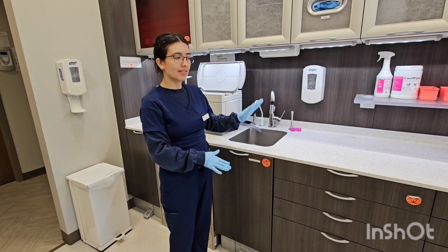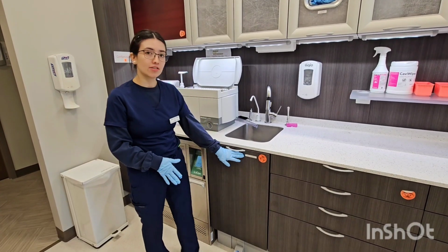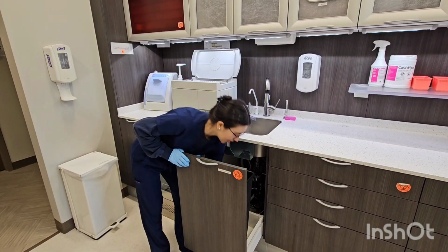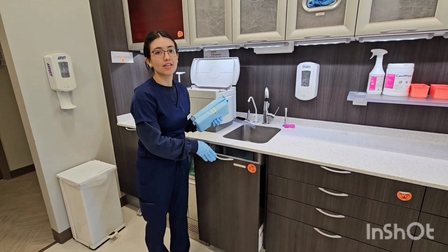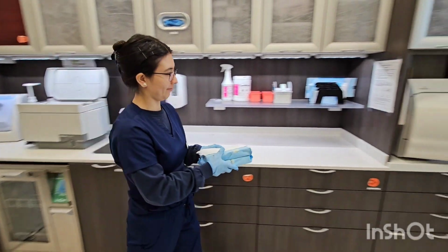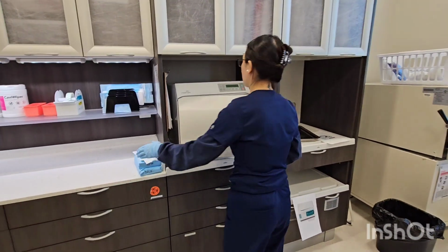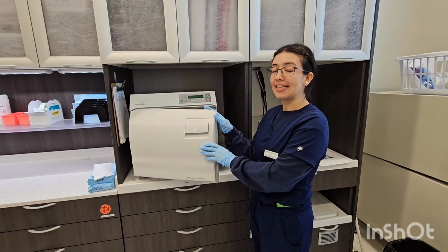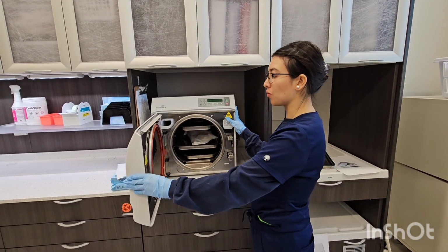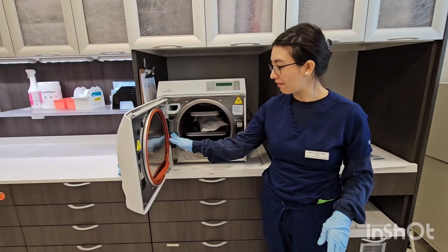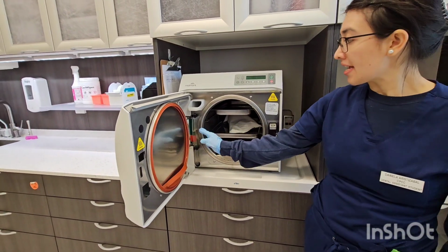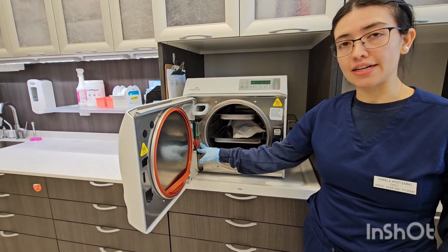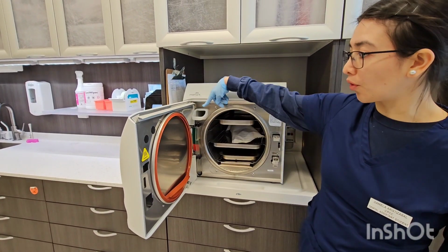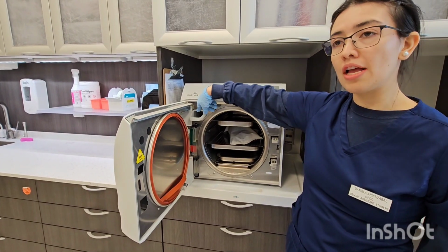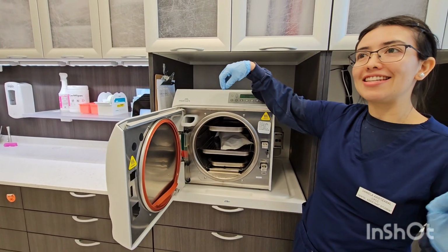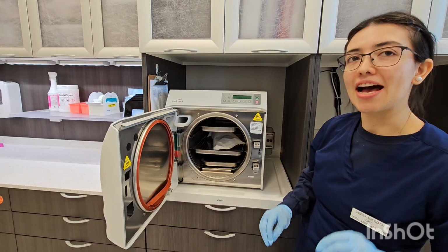So once the instruments have been packaged and they're ready to be sterilized, we are going to get them and go ahead to the autoclave machine. Before we place any instruments in the autoclave machine, we have to make sure that the water levels are in the green side. If they are lower on the red side, we have to pour more water into this hole, and it has to be distilled water. It cannot be tap water.